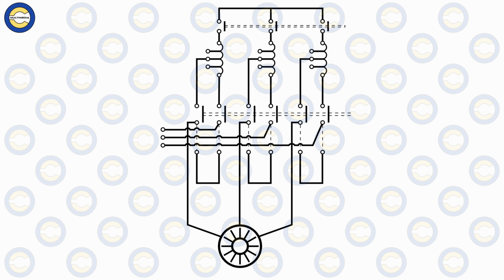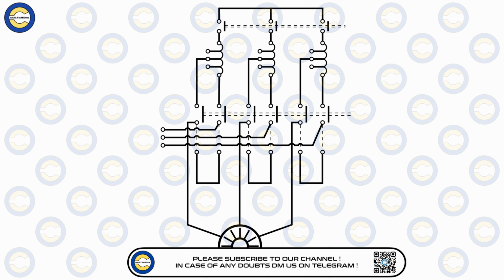The auto transformer starter reduces the starting voltage applied to the motor using a three-phase auto transformer. This particular transformer steps down the voltage during starting, and once the motor reaches about 80% of its rated speed, the motor is then switched to full line voltage for normal running, and thereby it attains its maximum running speed possible under normal operational circumstances.